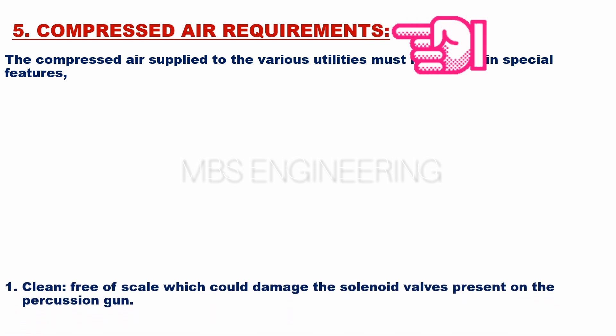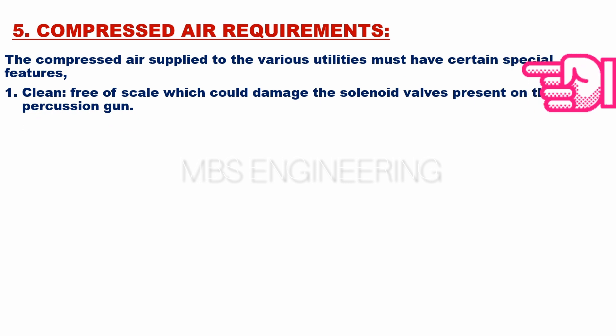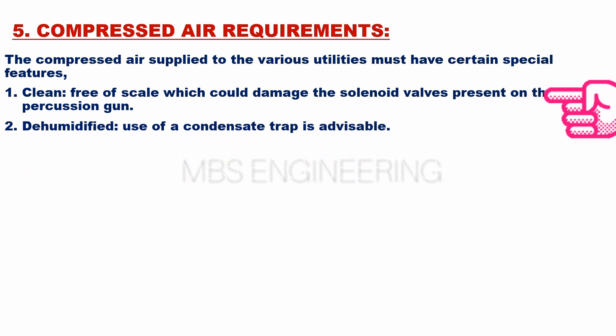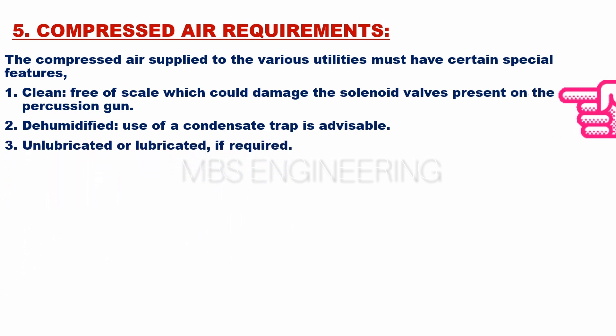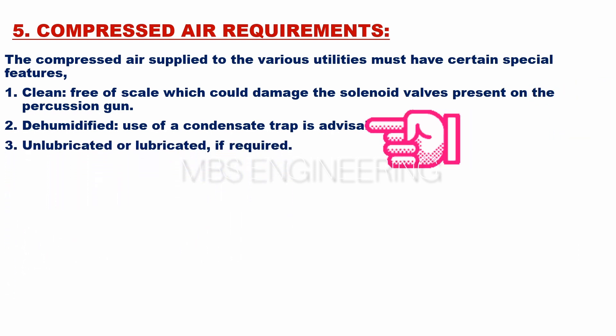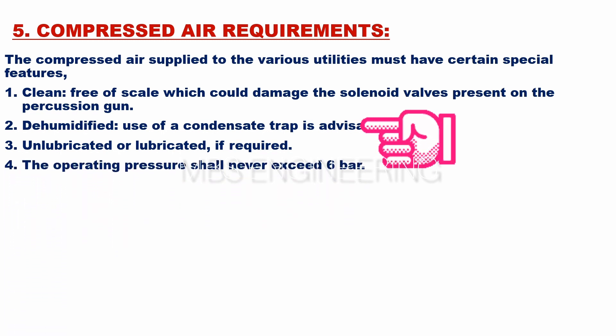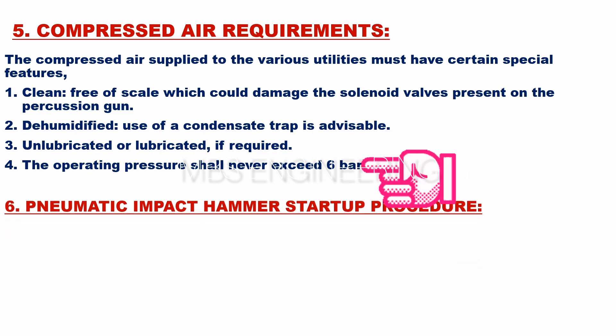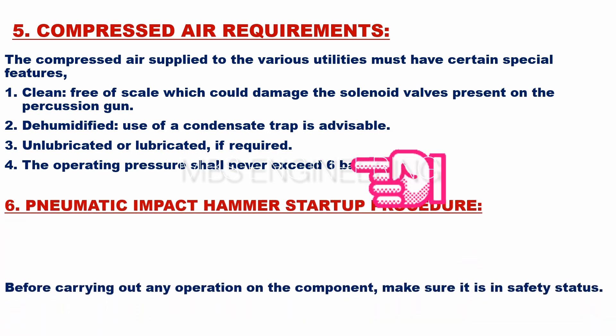The compressed air supplied to the various utilities must have certain special features. The first requirement is that the compressed air should be clean and free of scale, which could damage the solenoid valves present on the percussion gun. The second requirement is that the compressed air should be dehumidified — use of a condensate trap is advisable. The third requirement is that the compressed air should be unlubricated or lubricated if required, and the operating pressure shall never exceed 6 bars.